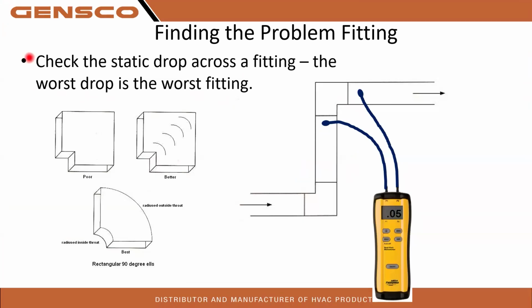Finding the problem: check the static pressure drop across the fitting. This can come into play, right? These square throats are horrible for airflow. These are poor because the airflow kind of skips over here. If we have a square throat, square heel, we want some kind of turn vane in there to direct that. Of course, radius heel, radius throat are the best for airflow. Minimize that static pressure.